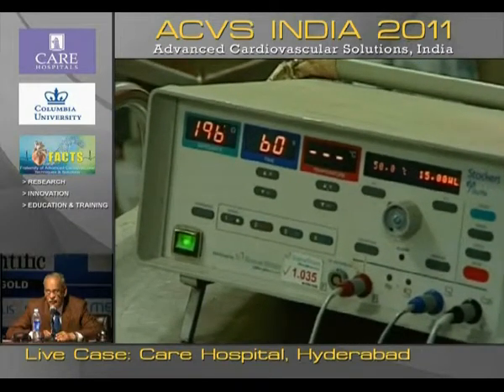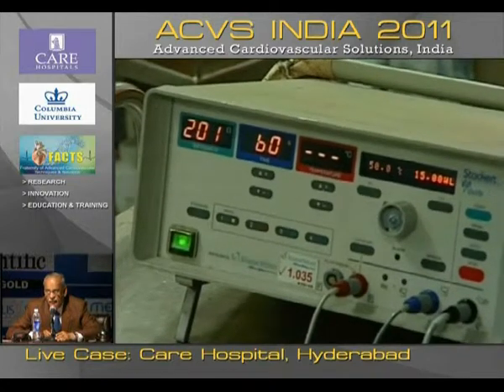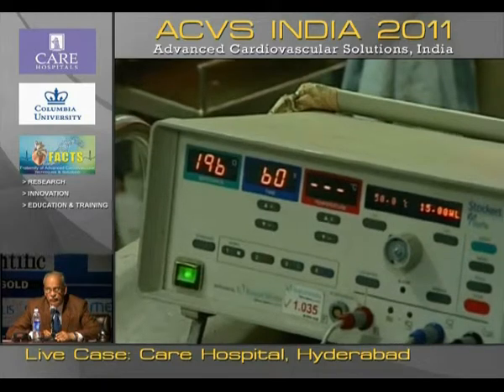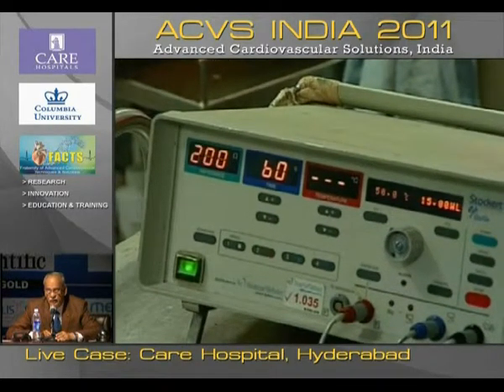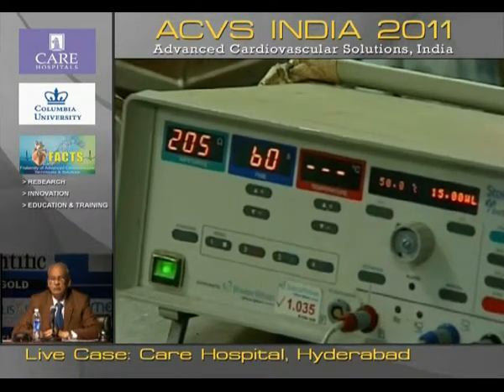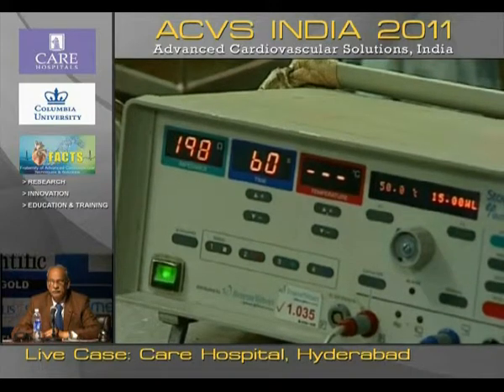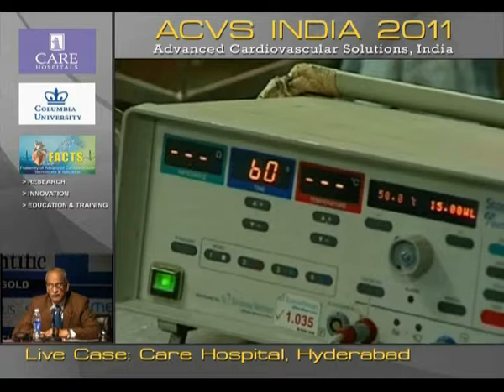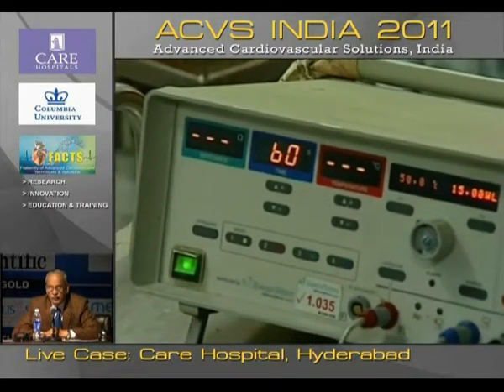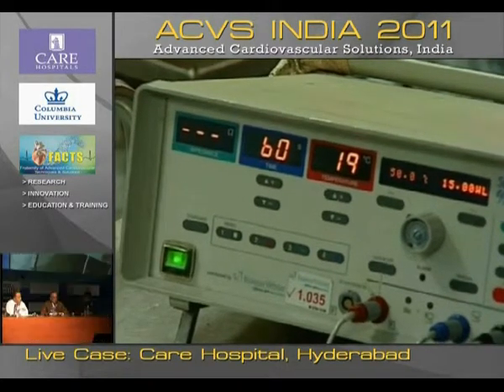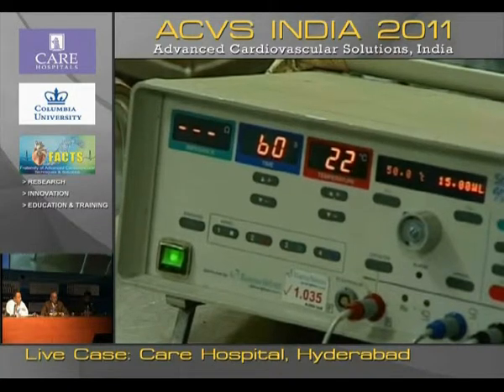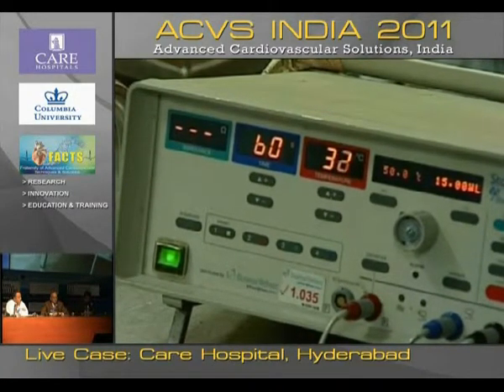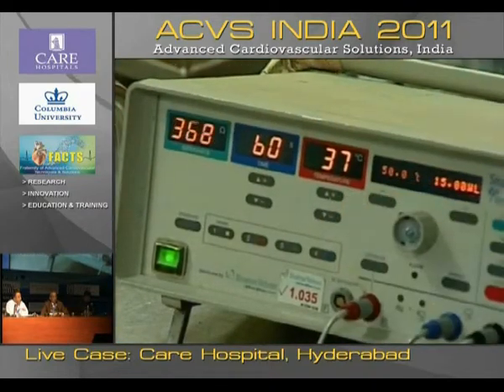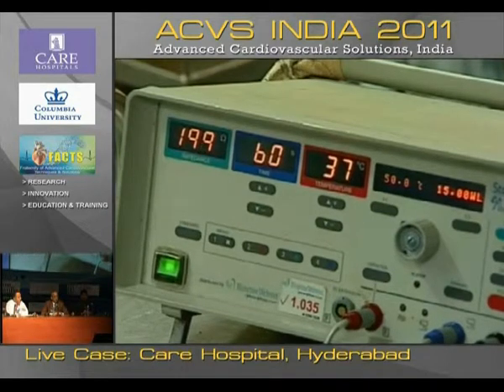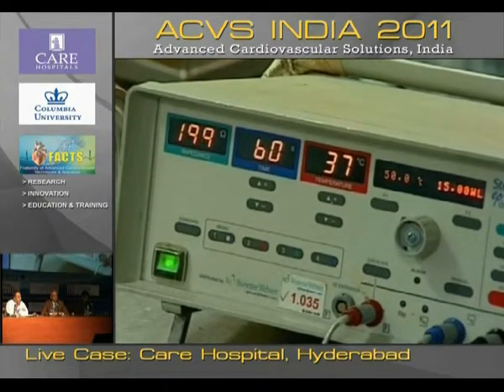Now as you can see, the moment it goes in, you should see a temperature which comes up to body temperature, about 37 degrees. And we set the temperature to about 50 to 55 degrees Celsius. This is quite important because the tissue heating is much higher than what you are setting. Even if you set 50, that is the tip temperature of the catheter, but the tissue temperature heats up to as high as about 60 to 65 degrees. That is why we are a little conservative with our temperature, to prevent coagulum formation and steam pops. The machine will automatically cut off when it exceeds 50 degrees. Okay, we are set now.